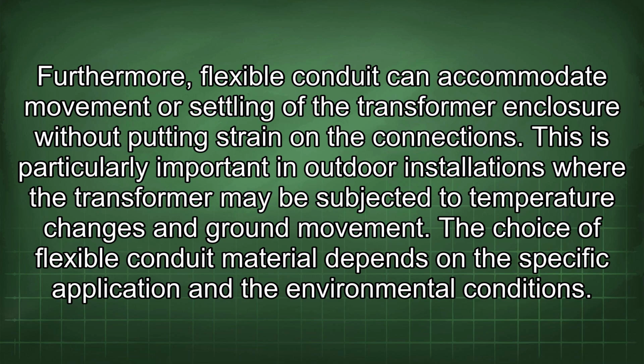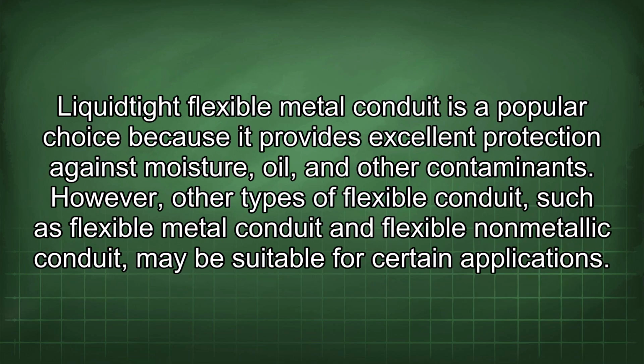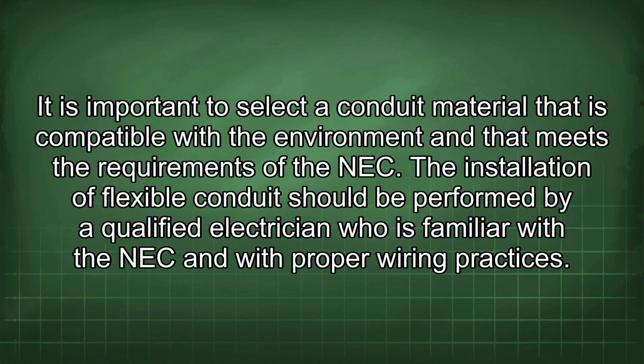The choice of flexible conduit material depends on the specific application and the environmental conditions. Liquidtight flexible metal conduit is a popular choice because it provides excellent protection against moisture, oil, and other contaminants. However, other types of flexible conduit, such as flexible metal conduit and flexible non-metallic conduit, may be suitable for certain applications.